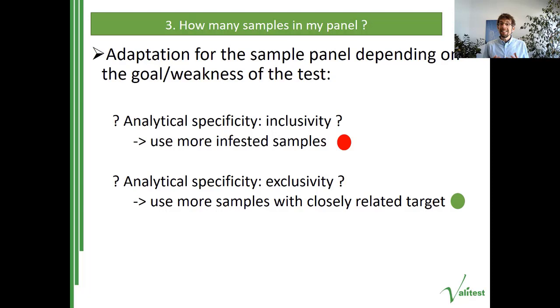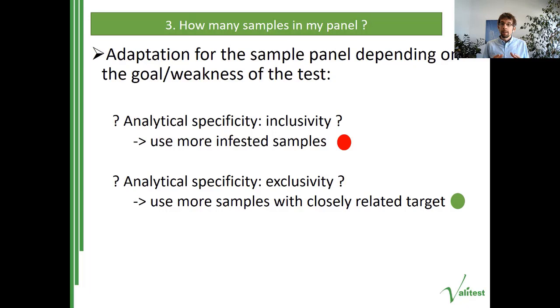This is a recommendation, but it is clear that you may need to adapt the sample panel composition depending on the intended use of the test and its potential weaknesses identified previously. For example, if you have a key question on inclusivity for analytical specificity, you can use more infested samples and fewer samples to evaluate analytical sensitivity. Similarly, if you fear difficulties related to exclusivity, you can use more samples with closely related targets to evaluate that specific criterion.